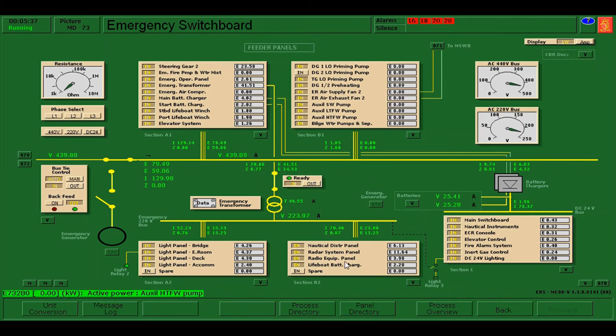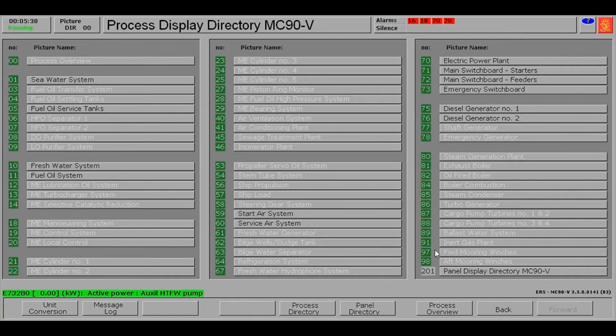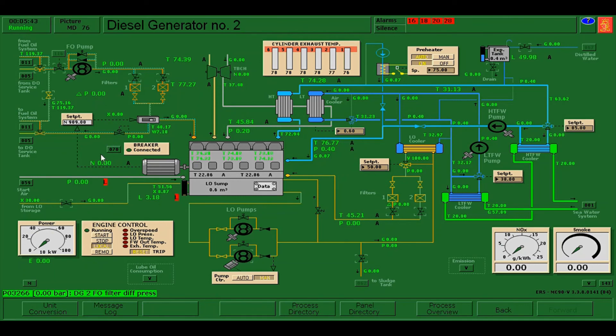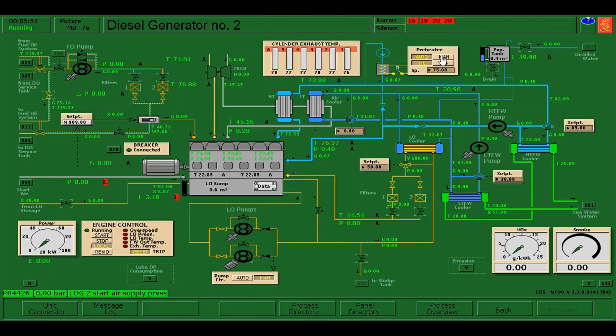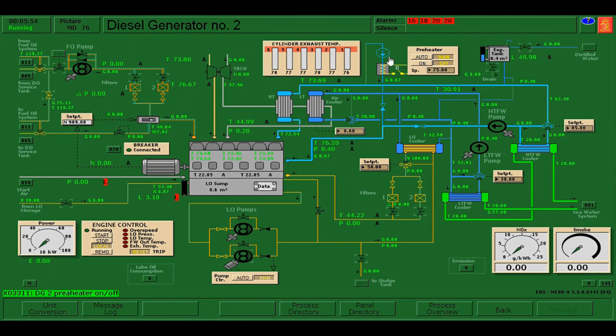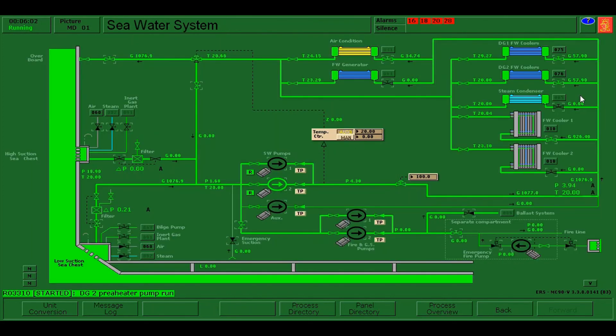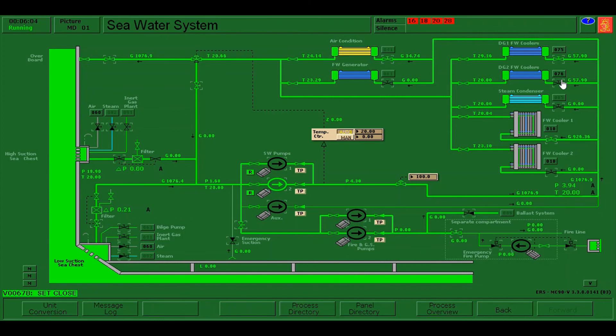Let's go back here. Fuel, air, lube oil is now isolated. We will now proceed on the cooling water. I'm going to put the preheater on manual and switch it off. After that, the sea water line, just need to close this valve going to DG2. That's it.